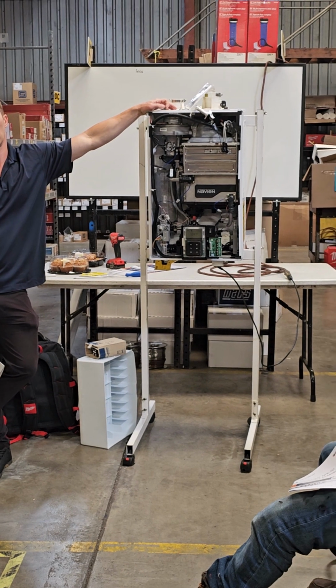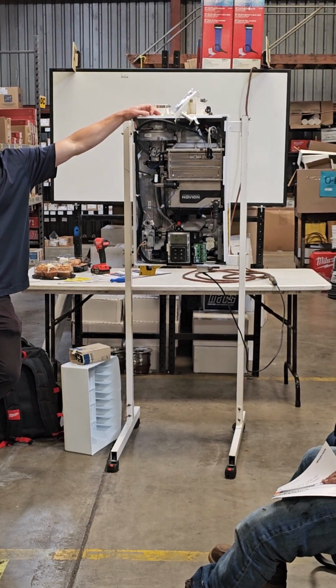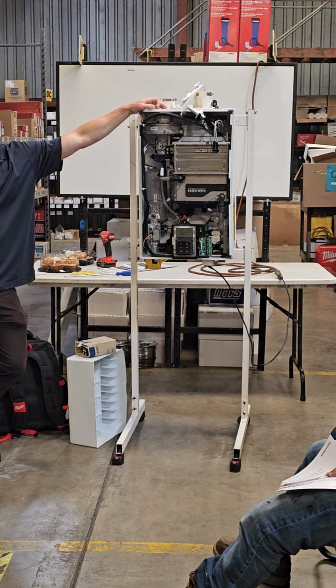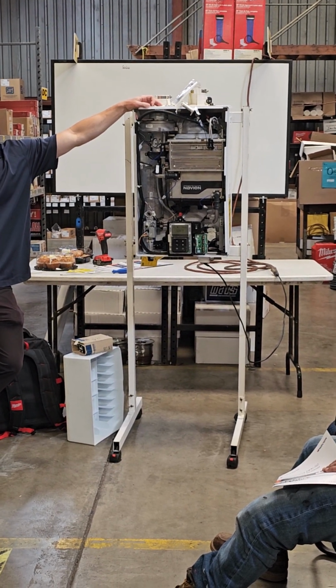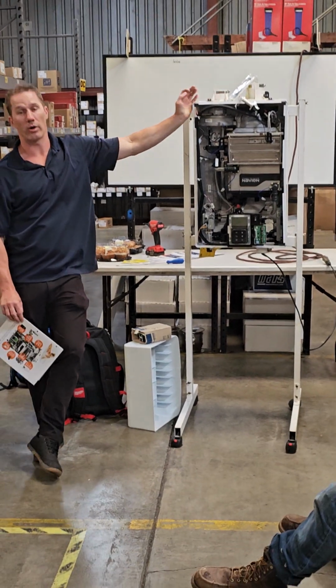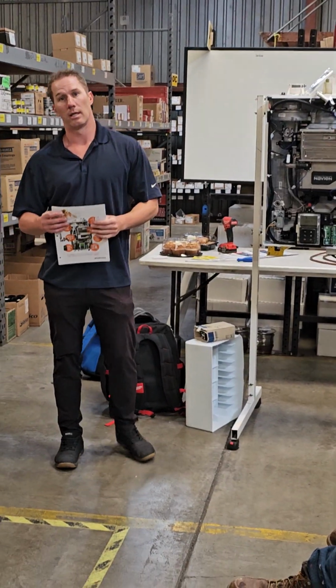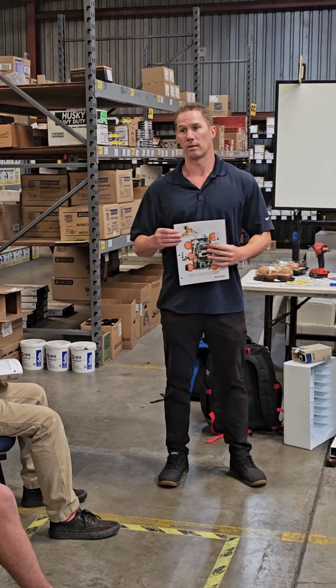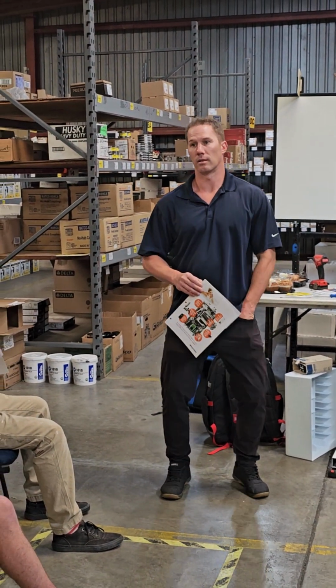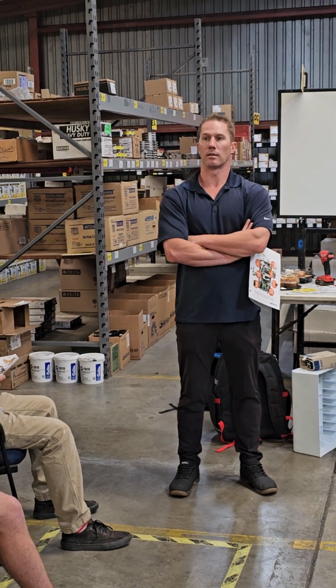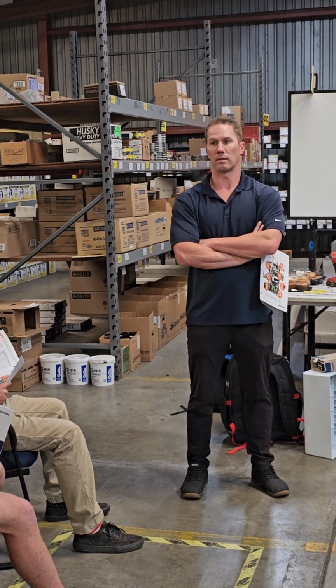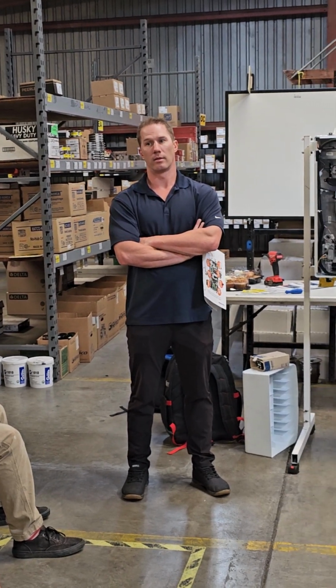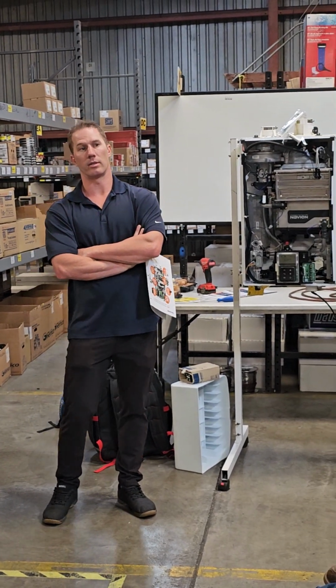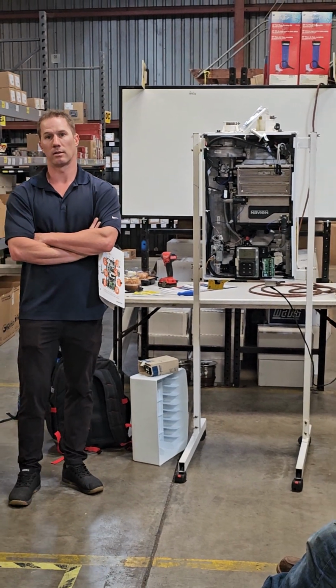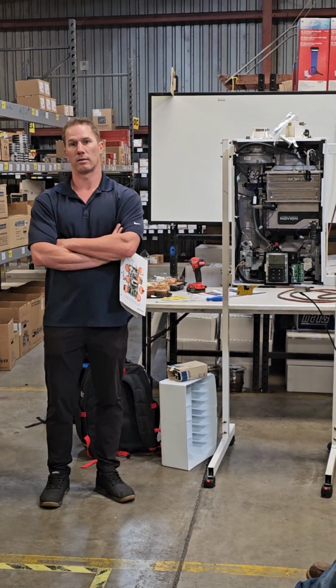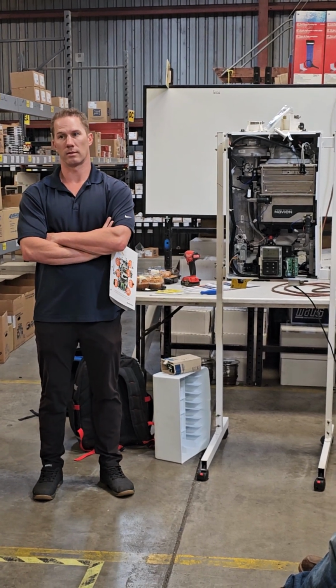Yeah, and this is more of a residential water heater. It's just that years ago I know it voided warranties, especially in applications with multiple tankless units. I hadn't heard anything about exterior pumps and warranties recently. It has to do with whether it's demand-based, on a timer, or how the recirculation works. Most recirc pumps now don't just run 24/7. If you use one of those old-style ones, yes, it will void it. But a lot of residential pumps do run continuously unless they've got a timer on them.